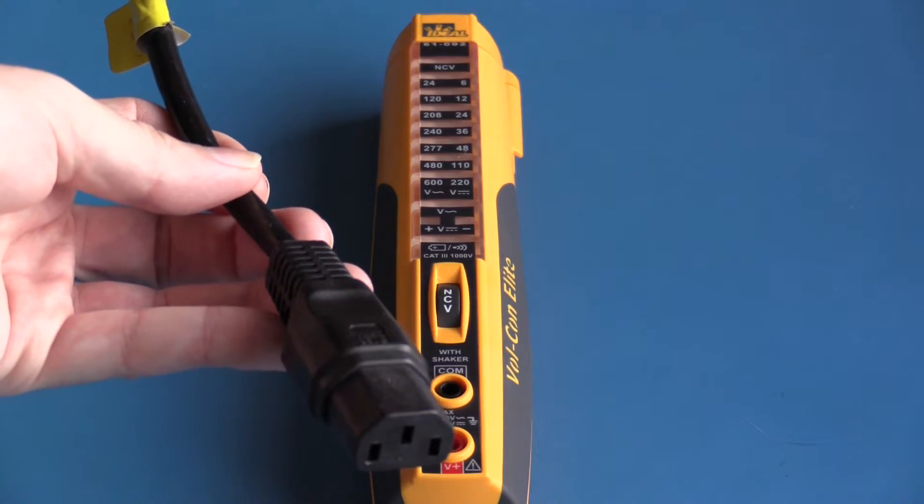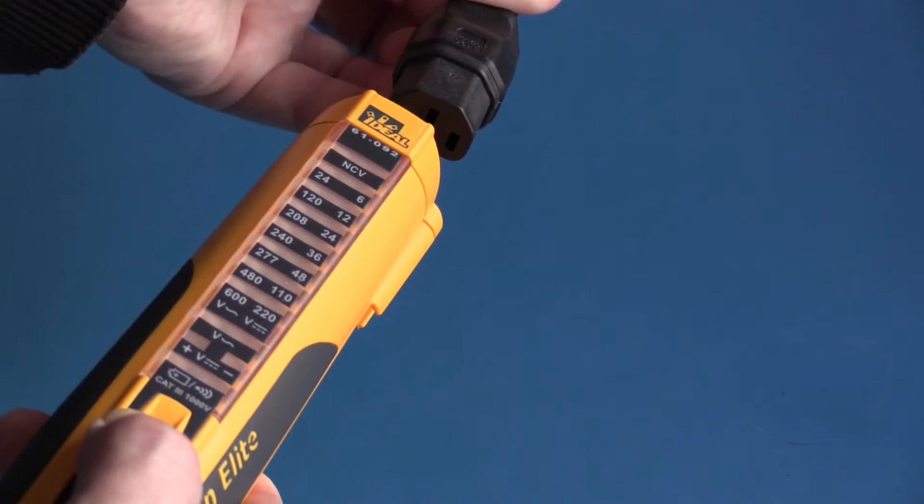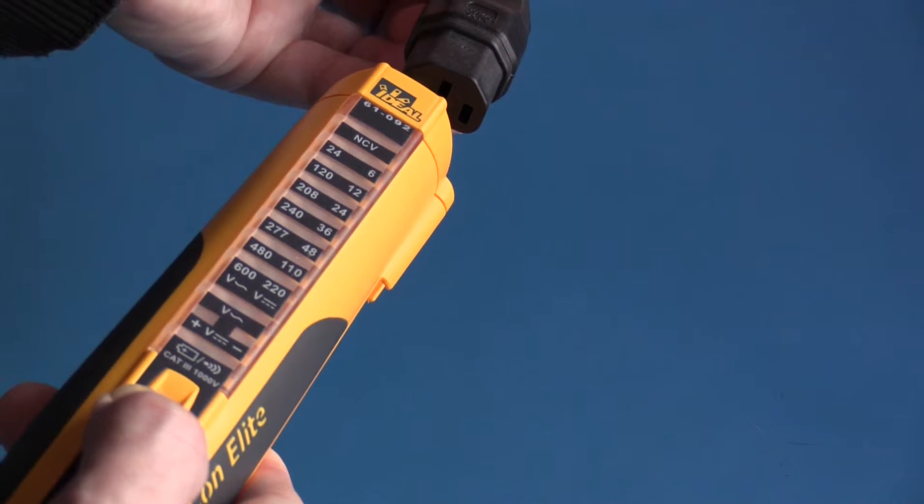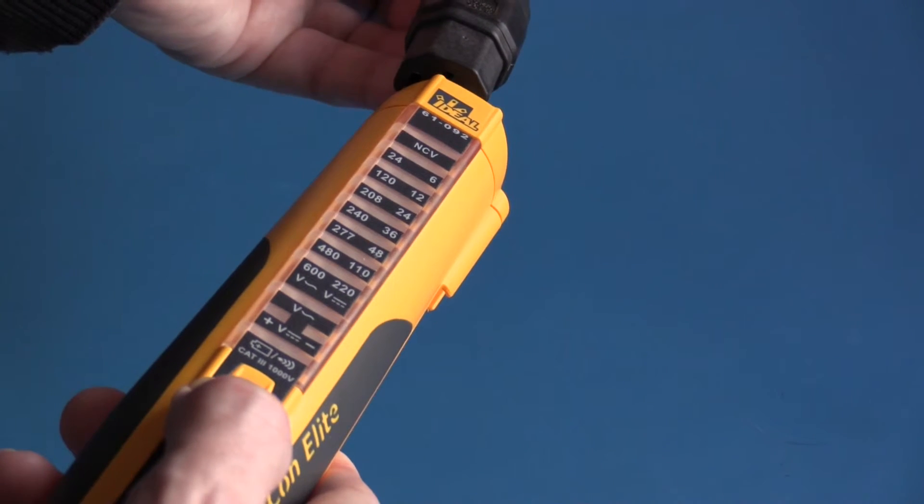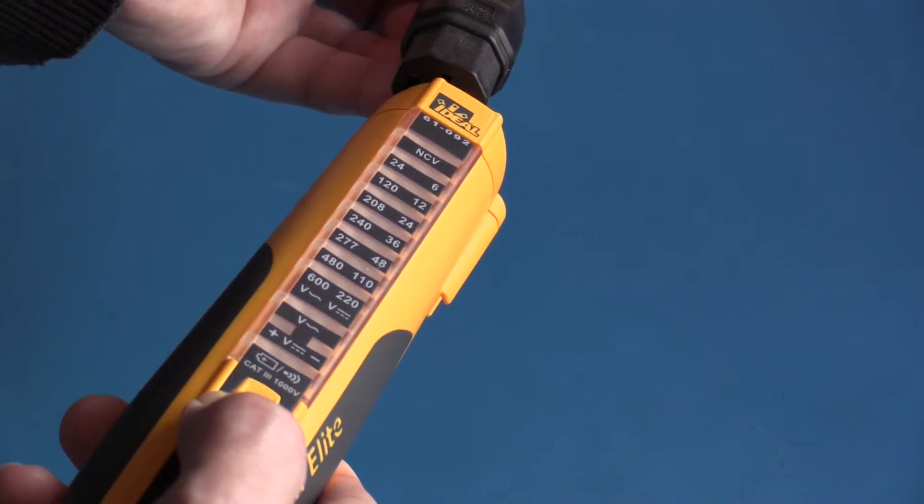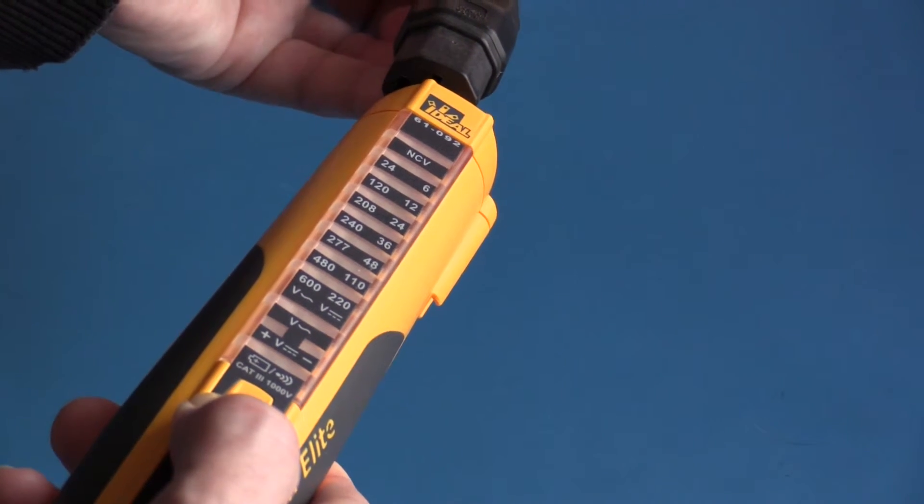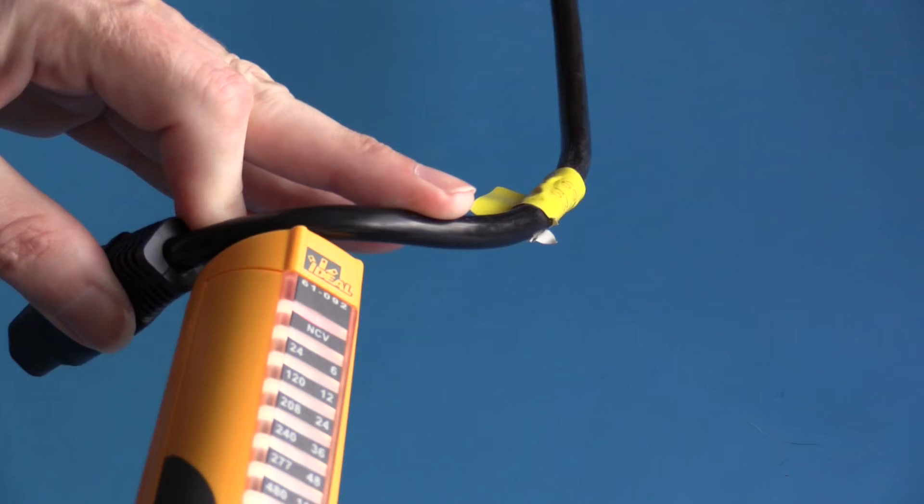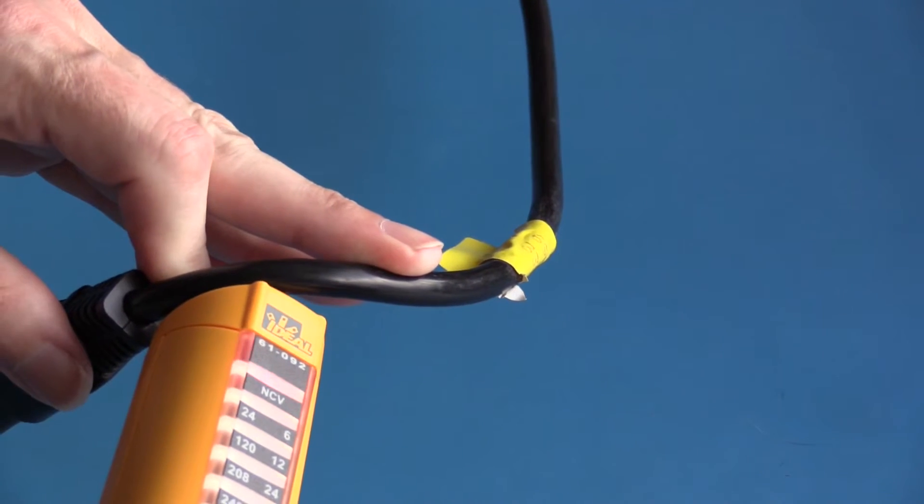This is a more substantial 10 amp rated cord neutral. We're getting no indication. Now let's check live. And we're also not getting indication of any voltage present. There's no indication that this cable is live when tested in this manner. But we can clearly see that this cable is actually live.